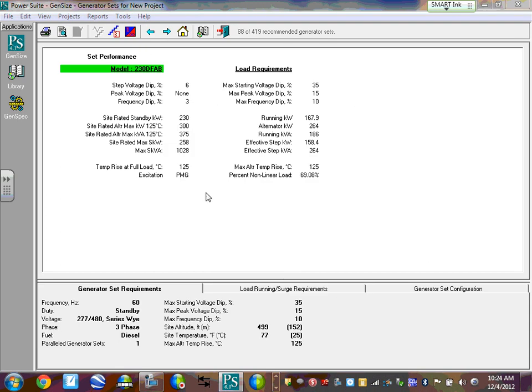It still picks a 230. And it's saying they've only got a voltage dip of 6% here, and the load could go up to 35. You can set the parameters up in the beginning of the program to be anything you want as default. 35 is a little heavy. You could have motor contactors dropping out at that. So bring it up to 30 or maybe 25 would be a good design parameter.